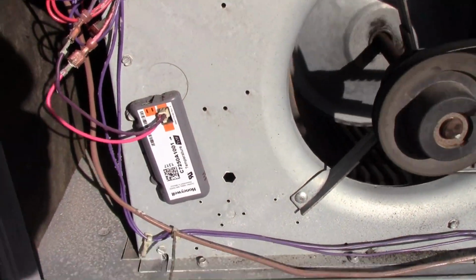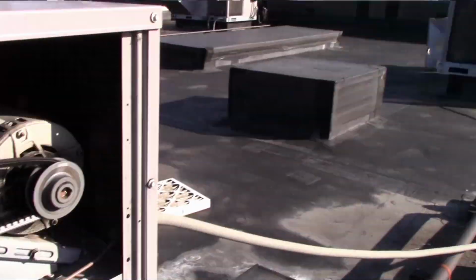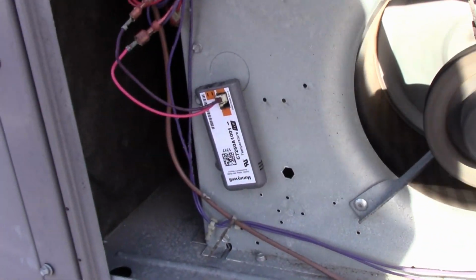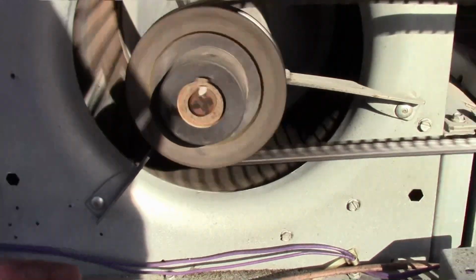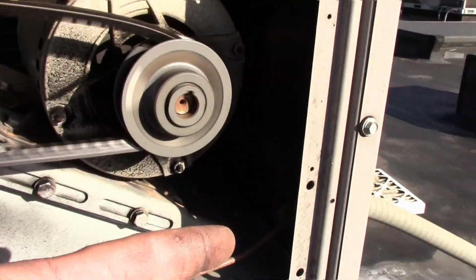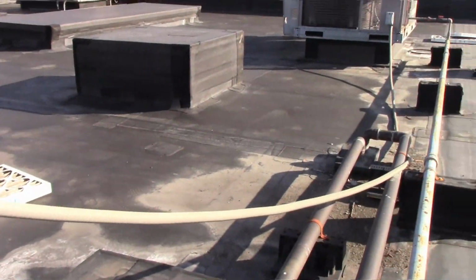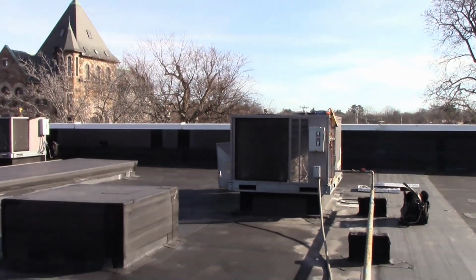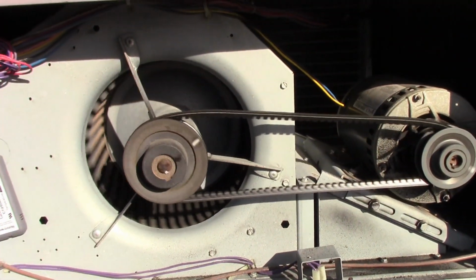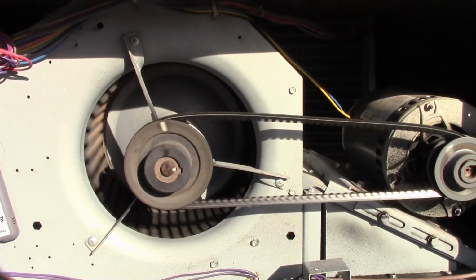So rather than pulling 2 thermostat wires through the building, they pulled 2 up into this unit and along the inside of the blower section through that piece of liquid tight and into the other unit. That's cute. Alright, I can change this belt too. Whew, a little cold. So everything's all set with those 2 units.